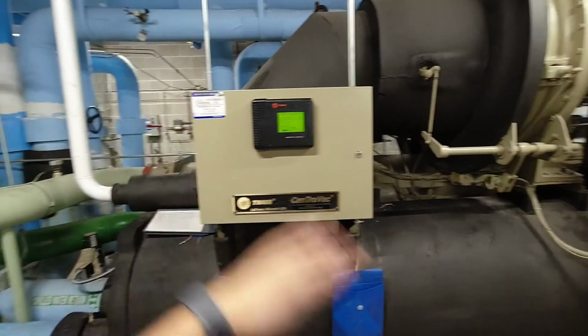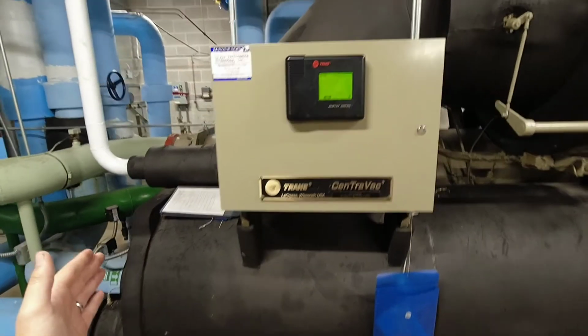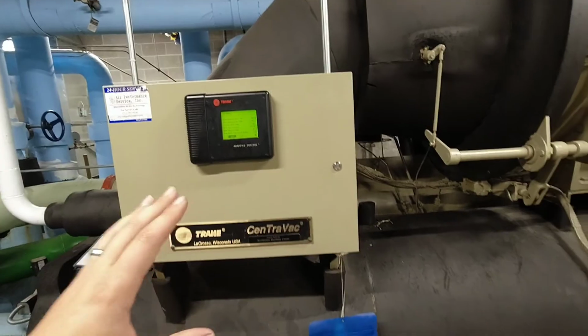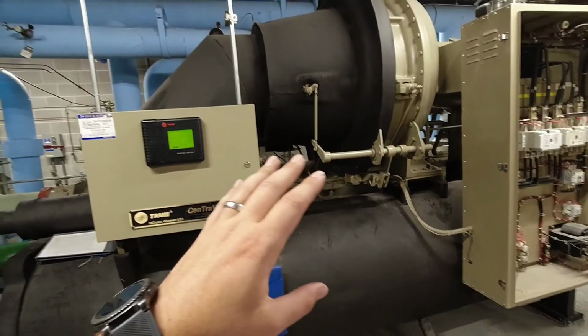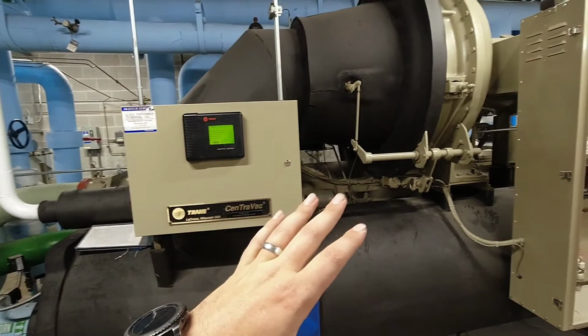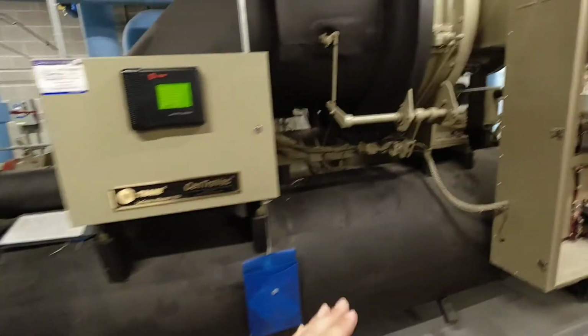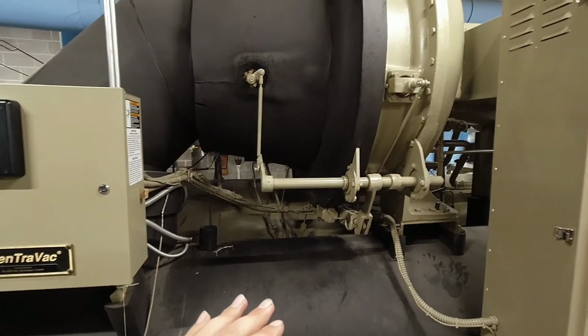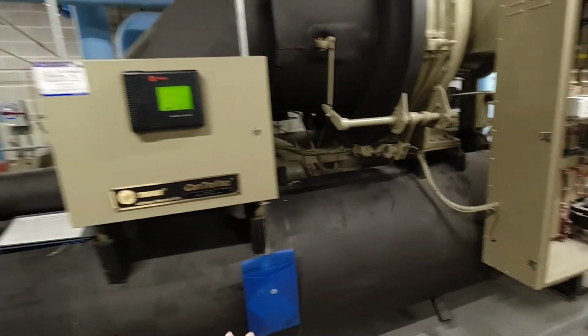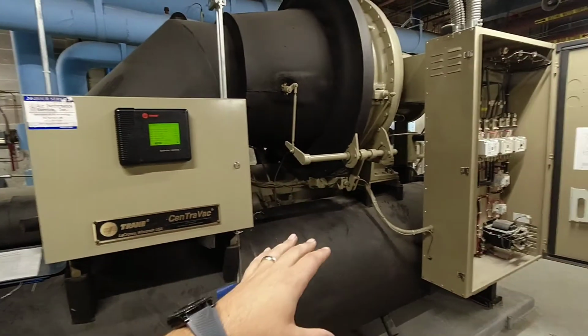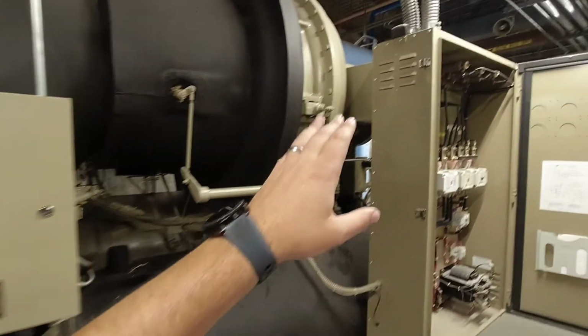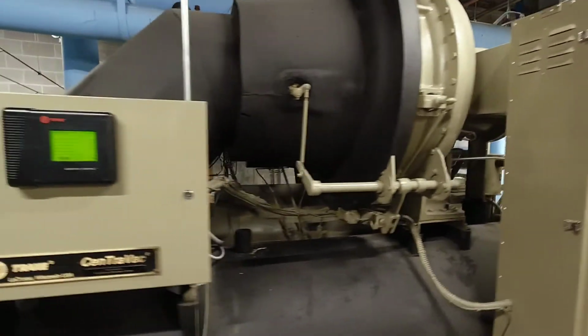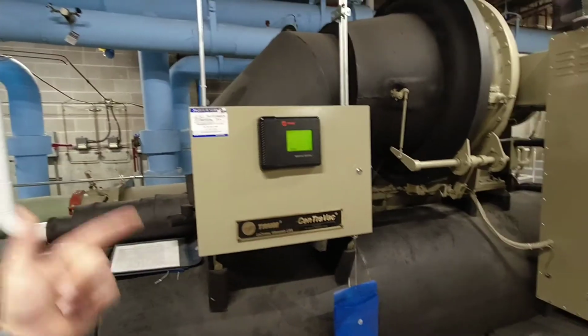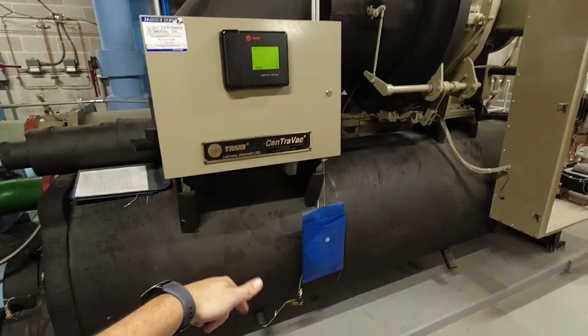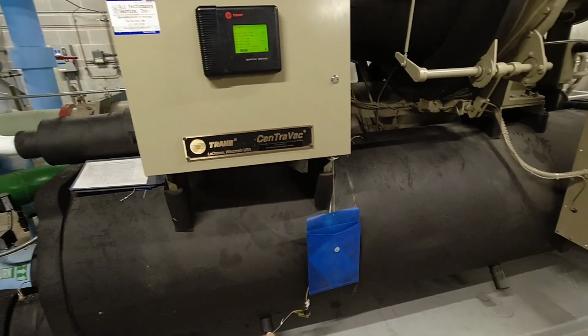That is because it's not running at a stable operation, and that temperature sensor cannot fluctuate like the pressure is fluctuating. So you have to take that into account when you start doing heavy troubleshooting, especially with things like surging. You can't trust those numbers completely. You're going to have to put your own gauges on it to get your own baseline as to what's actually happening live in the system. The only transducers this thing uses, like on the oil pressure, is an actual transducer, but the refrigerant pressures are strictly conversions of a temperature, and those need to be very, very accurate.